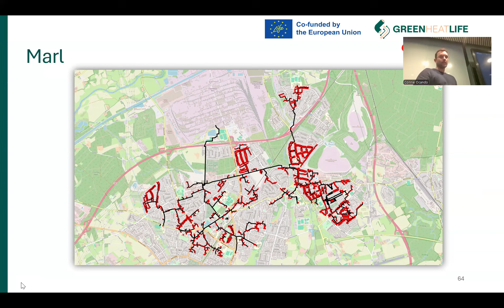The digital twin showed us that we are operating the district heating system at very high temperatures. We know this, of course, but the digital twin showed us where we have these high temperatures, nearly in the entire network, so also in the outer pipes. And we know that the customers do not need these high temperatures, so they can also be supplied at lower temperatures, below 100 degrees Celsius. So we decided to focus here on temperature reduction.